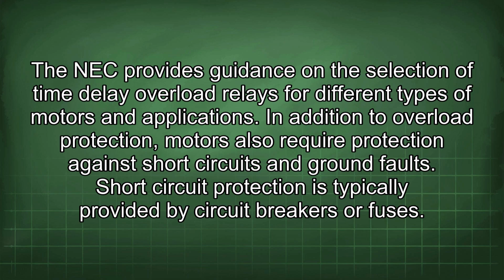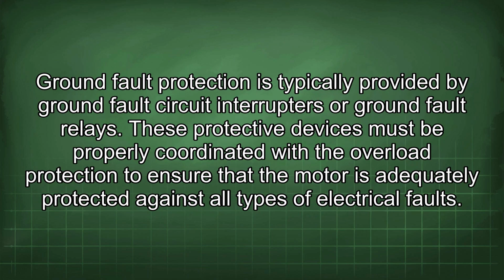In addition to overload protection, motors also require protection against short circuits and ground faults. Short circuit protection is typically provided by circuit breakers or fuses. Ground fault protection is typically provided by ground fault circuit interrupters or ground fault relays. These protective devices must be properly coordinated with the overload protection to ensure that the motor is adequately protected against all types of electrical faults.